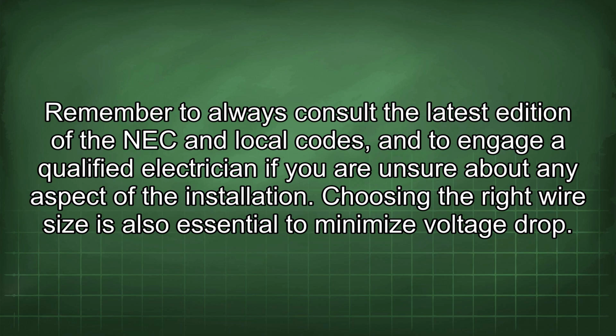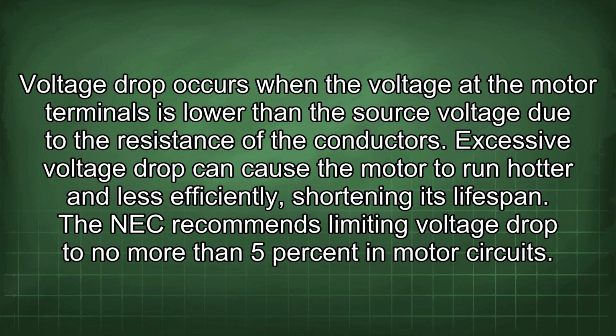Choosing the right wire size is also essential to minimize voltage drop. Voltage drop occurs when the voltage at the motor terminals is lower than the source voltage due to the resistance of the conductors.